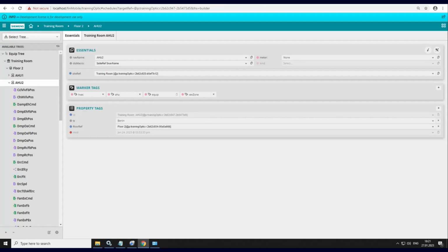I want to make a note. Before you start on graphics, you need to set up a couple of things. Your alarms and your trends must be set up as much as possible because they tag some points when that's performed, which will affect the graphics. If you make a change after, you must update the binding. I highly recommend that, 1. You create the alarms you need to, and 2. You create the trends.